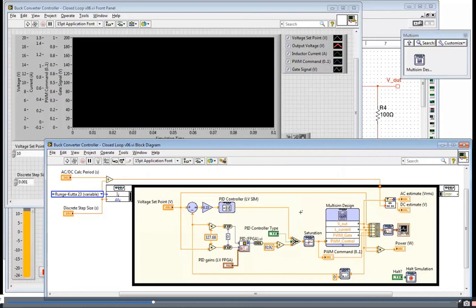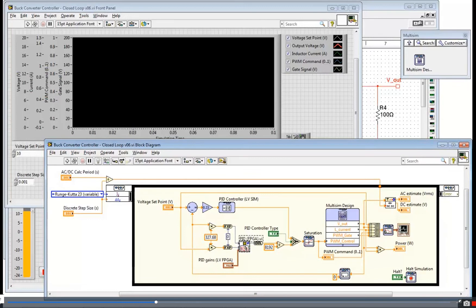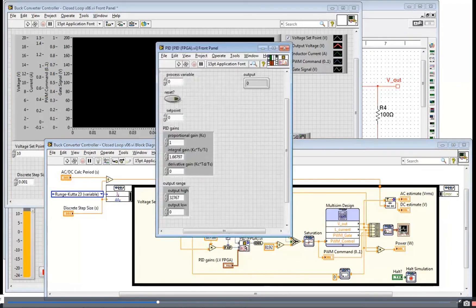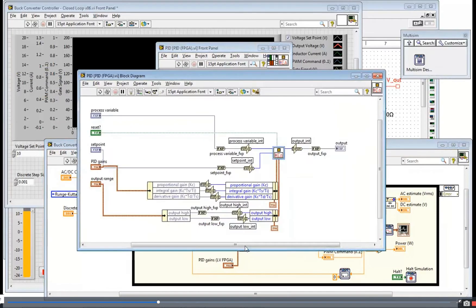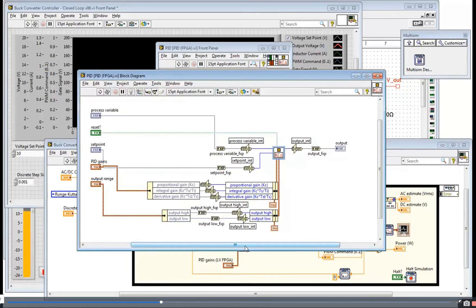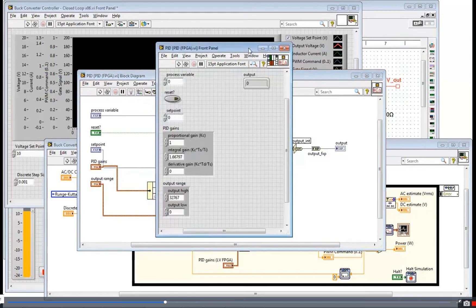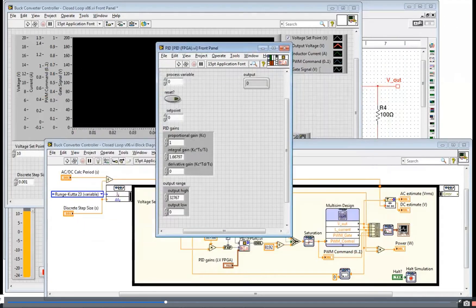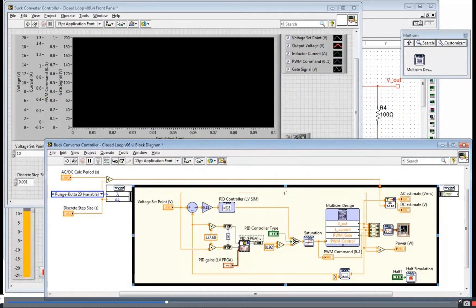But the important thing I want to show you here is the ability to actually put LabVIEW FPGA code. Because most of the time, your control systems for your inverters are going to be running in LabVIEW FPGA. And so this is my actual LabVIEW FPGA code. And that's one of the big benefits of this tool chain is I develop my code in co-simulation and I preserve that code investment all the way throughout my development. And I can validate all my code before I actually compile it to the FPGA, which helps me deal with the fact that FPGA compiles do take a long time compared to processors.